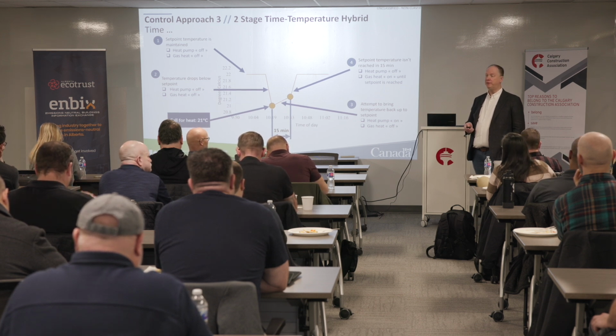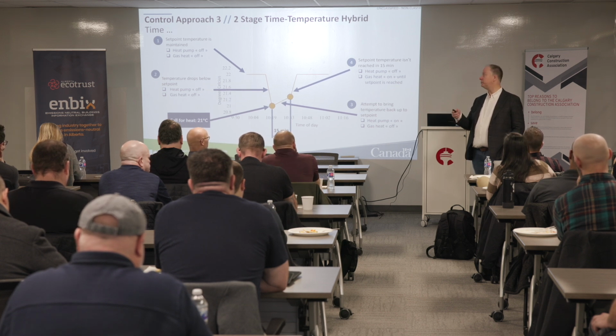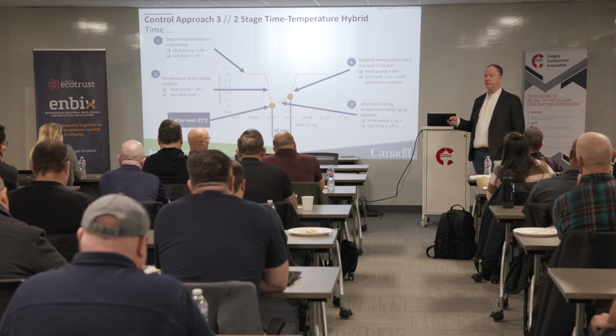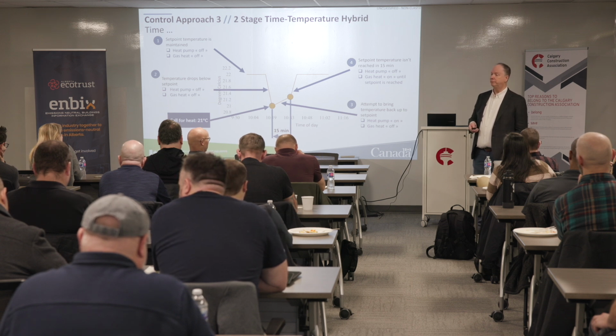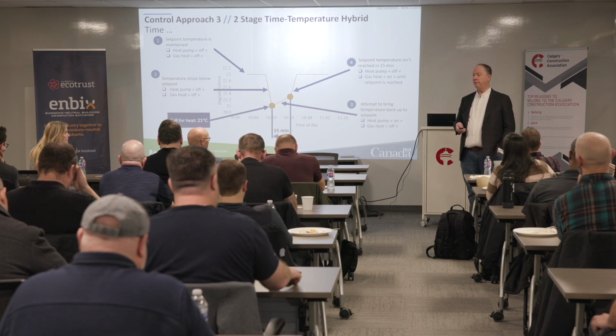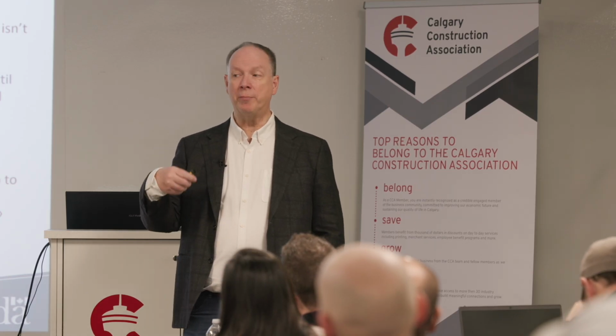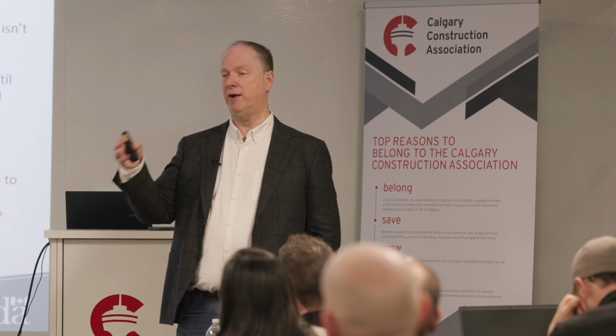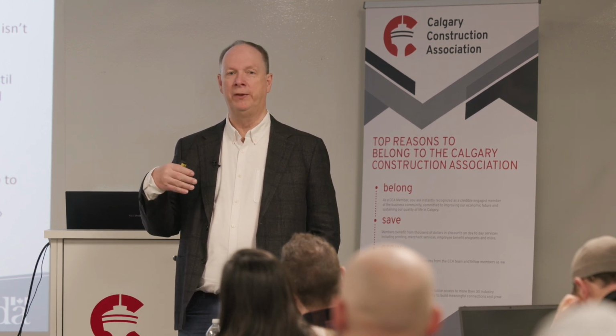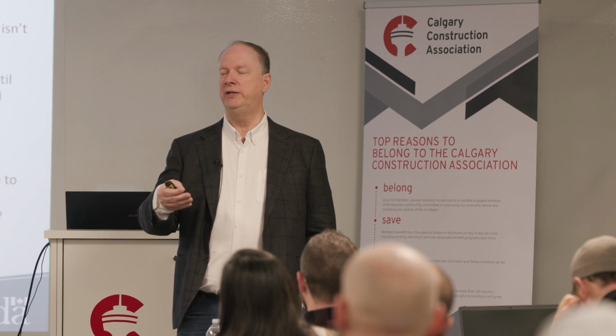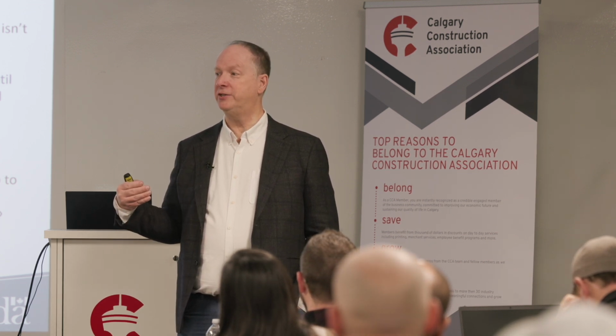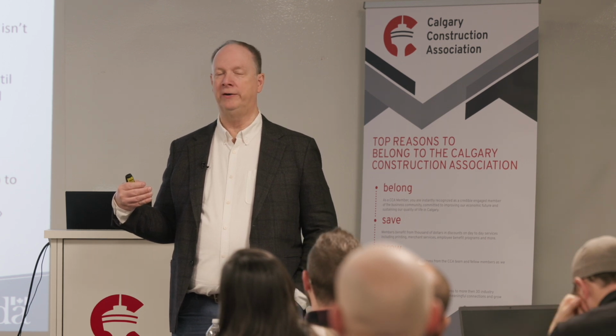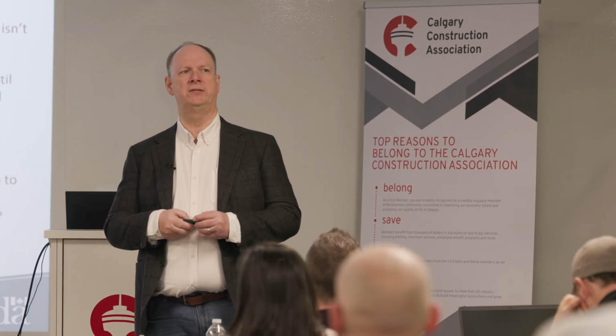When we're installing these, we can use certain control systems that give the heat pump a little longer to work. We ask the customer to change their set point in stages, so the heat pump comes on within that 1.5 degree range. We ask the client to make a few changes to how they operate the home, and that drives the point home. It's an excellent example of how we can't just install this and walk away. There's a certain amount of education required on our part, and I'll throw myself under the bus for this.